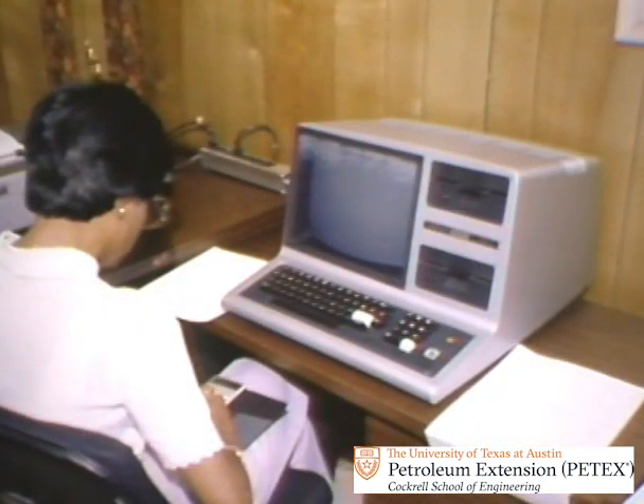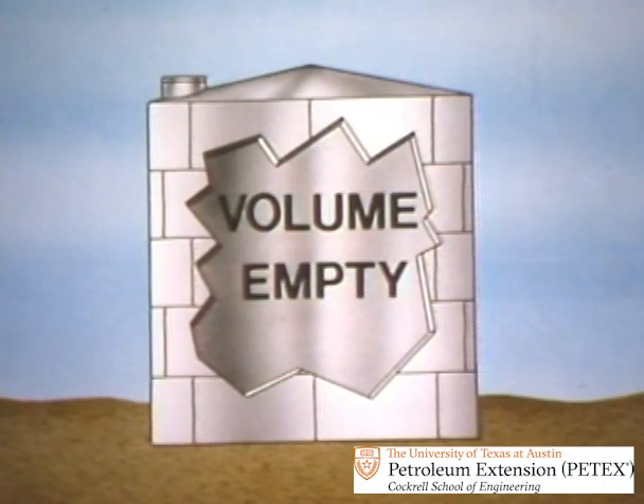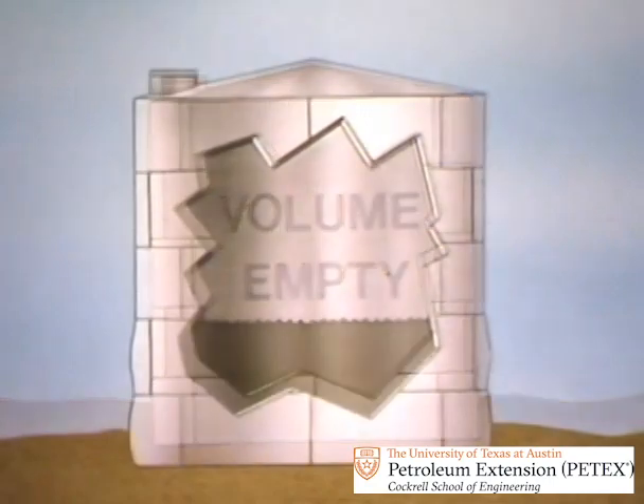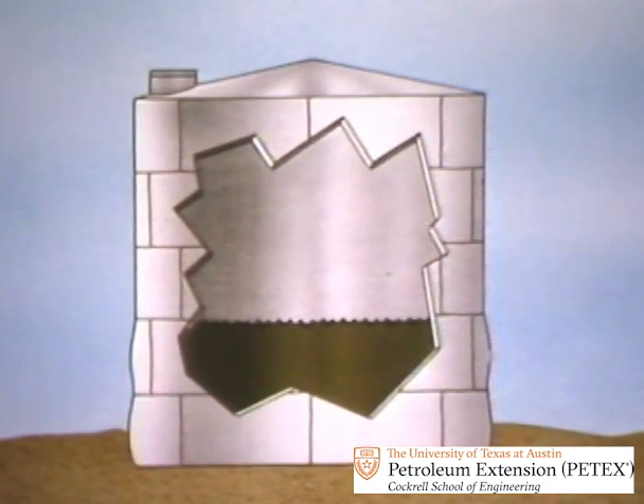So the person calculating the capacity table will take the temperature, gravity, and liquid height figures and compute the liquid head stress at the time the tank was strapped. Then they'll mathematically empty the tank and figure the volume. Of course, if the tank were strapped empty, this volume calculation wouldn't be needed. Finally, they'll mathematically fill the tank, adjusting the table for shell expansion as each ring is filled. The capacity table will be correct for any condition of fill.